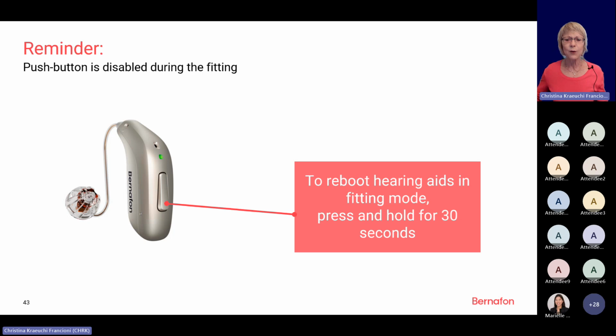So in this situation, it is possible to disconnect the hearing instrument from the fitting software, and we must put them in hard reset mode. In order to activate the hard reset mode, just press and hold down the push button for 30 seconds. Hold on for 30 seconds, maybe check on your watch. It actually needs 30 seconds to reboot the hearing instrument completely. 15 seconds would not be sufficient, therefore take your time. After 30 seconds, the hearing instruments will be rebooted completely and you can start the fitting again. And don't worry, no data in the hearing instruments will be lost.